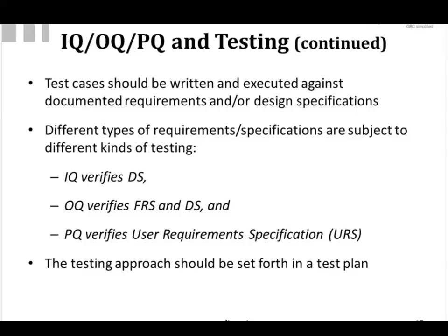Now, IQ and OQ can be done by an outside source. It can be done by a vendor. And you can purchase IQ and OQ packages that would include protocols and test scripts and scenarios for the OQ. You want to make sure that if you've done that, you're using a vendor that you've audited at least every other year, that that vendor is one that is going to deliver against FDA compliance requirements, and that you've also made sure you have the right documentation in place.